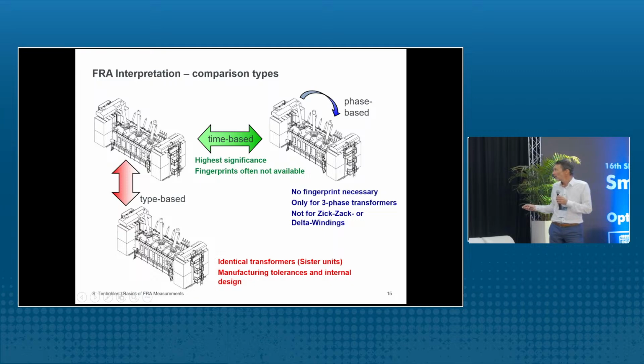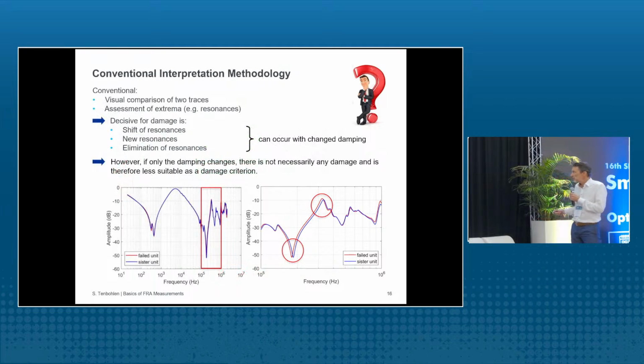Of course, best is to have a time-based comparison, also phase-based. Type-based can be difficult, because maybe the manufacturer has changed the design a little bit and you do not know this, and then you can get different responses, although the transformer is okay. And then you have two frequency responses, and let's say here are two units shown. If you look at the full frequency band, so this is up to 1 megahertz, both curves look pretty much the same. But if you start to zoom in, you see, okay, there are some differences. So, is this now okay, or is it not okay?